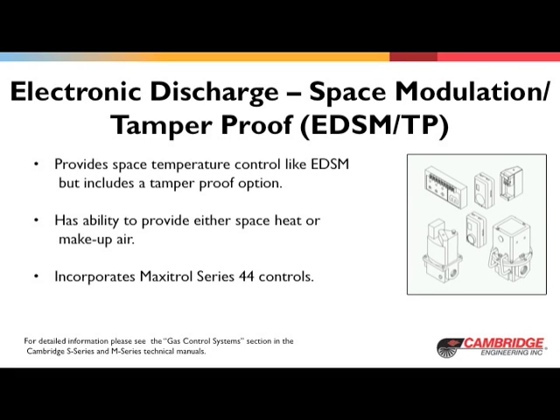Electronic Discharge Space Modulation Tamper Proof, or EDSM/TP. EDSM/TP may be used on both the S- and M-series products. EDSM/TP provides space temperature control. The discharge temperature modulates based on a space temperature set point, or STS. TP, which stands for tamper proof, allows the space temperature selector to be mounted inside the lockable remote control station, and the tamper proof stat to be mounted outside of the remote control station. EDSM/TP provides space heat and makeup air.